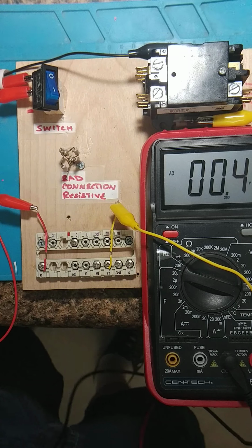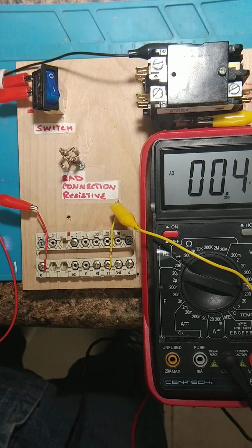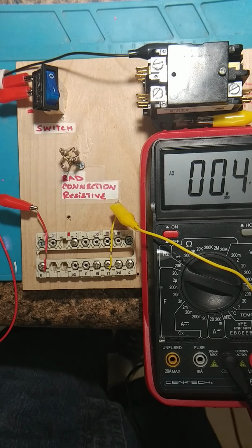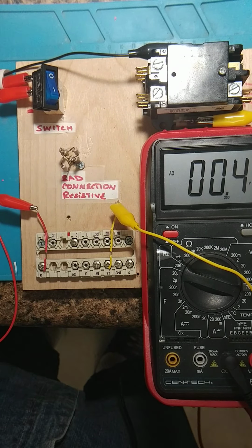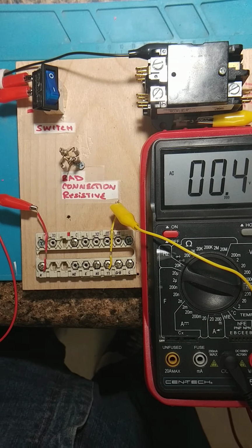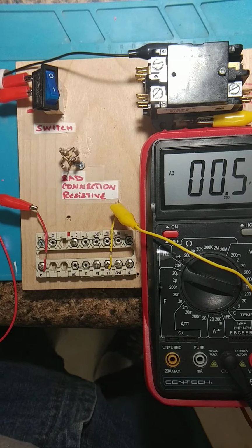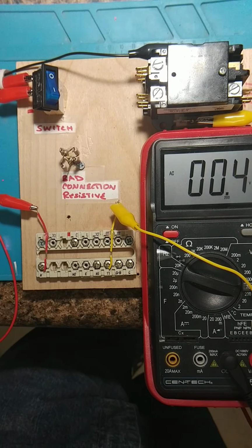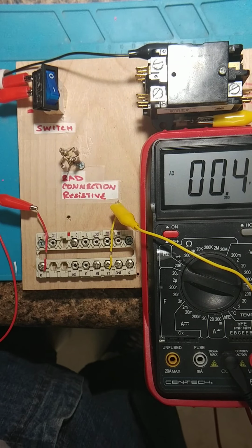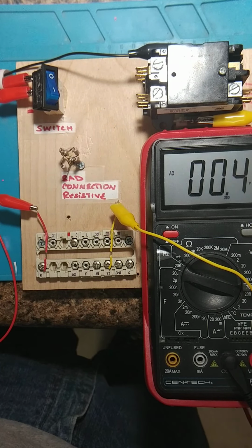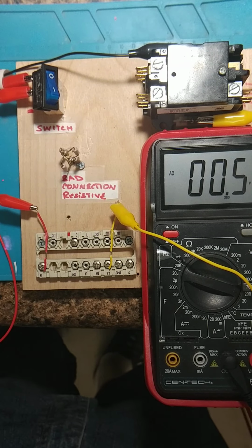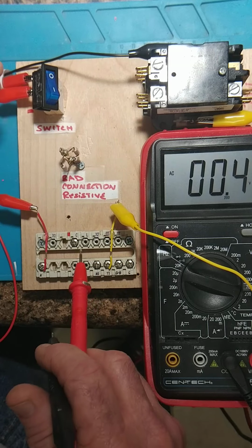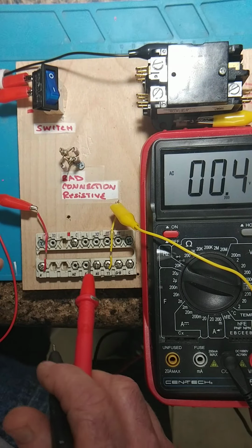So that's why when you're going to trace out a circuit for voltage drop, you're better off putting the thermostat in cool mode, fan on if you're tracing out the cooling circuit, fan on so you know the thermostat is closed. Then you can trace out your voltage drop to see where your open is. If your thermostat is off the sub base, then you've got an open in your thermostat. So it's going to be a lot harder for you to trace out an open somewhere else in your circuit.